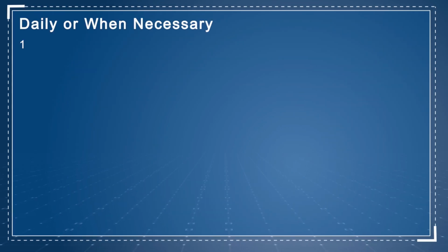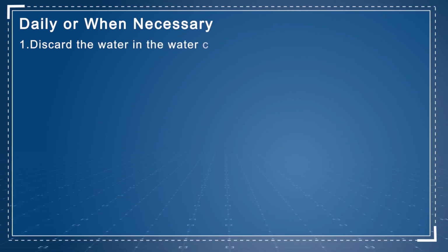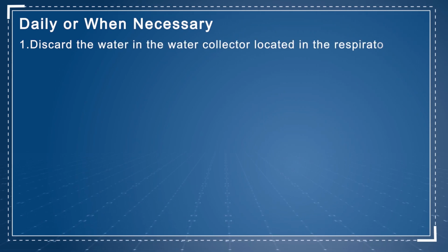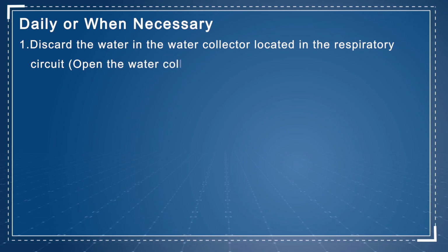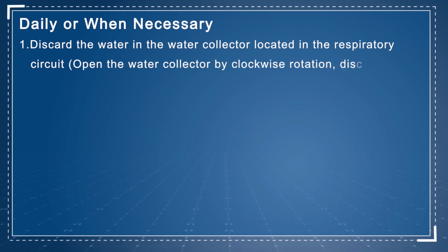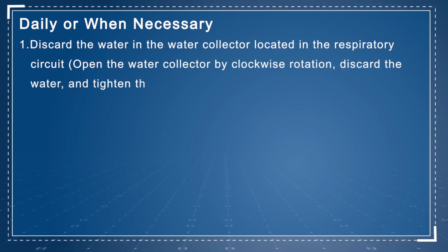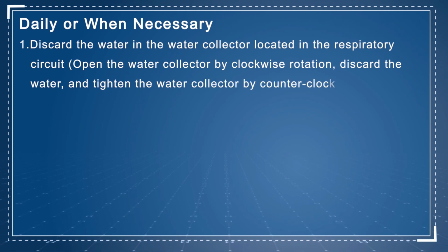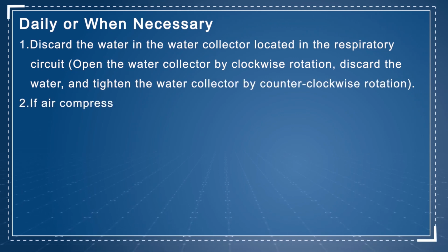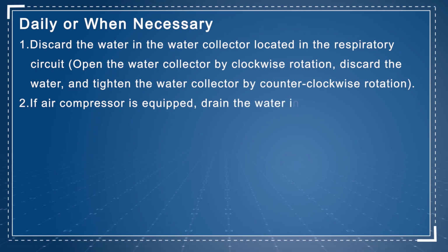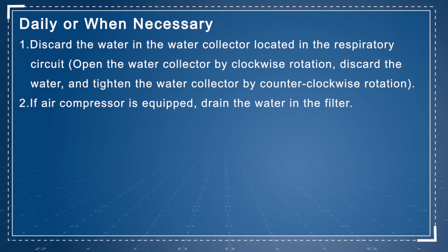Daily or when necessary. 1. Discard the water in the water collector located in the respiratory circuit. Open the water collector by clockwise rotation. Discard the water and tighten the water collector by counterclockwise rotation. 2. If an air compressor is equipped, drain the water in the filter.